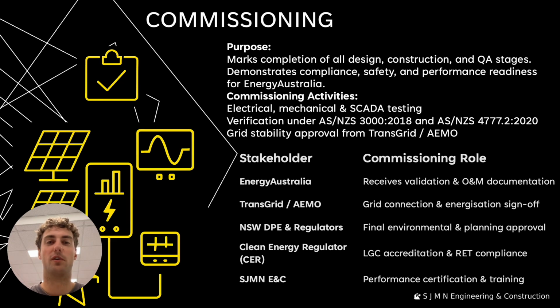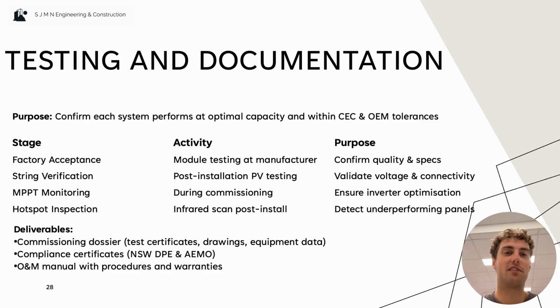Commissioning marks the point where all design, construction and quality assurance work is proven in the field. It includes mechanical, electrical and SCADA testing under Australian Standards 3000 and 4777.2. Stakeholders like Energy Australia, Transgrid, AEMO and the Clean Energy Regulator each play a role, from grid compliance and environmental approval to LGC accreditation. Every component is validated through factory acceptance testing, string verification, MPPT monitoring and infrared hotspot inspections.